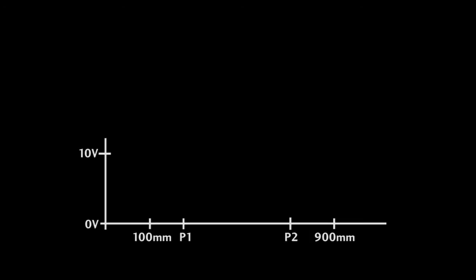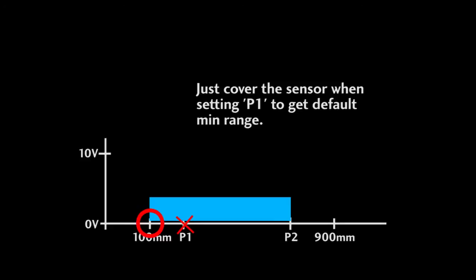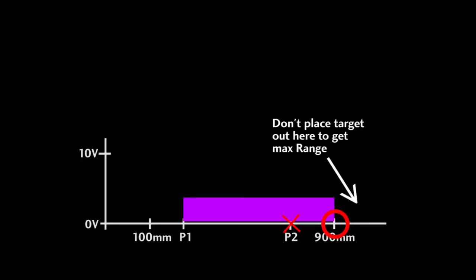Suppose you just want to detect all the objects from the minimum possible range to some fixed point. Well, that's easy. Just cover the sensor when you set the min range. It will default to the min. That doesn't work for the max range. Don't set the sensor distance past the max rating for the sensor – in this case 900 millimeters. It may give you unpredictable and unrepeatable results.